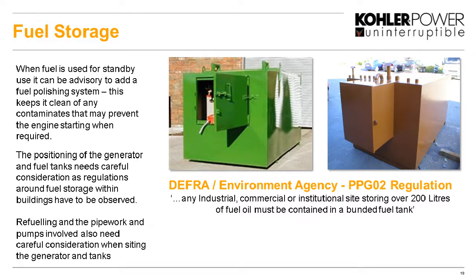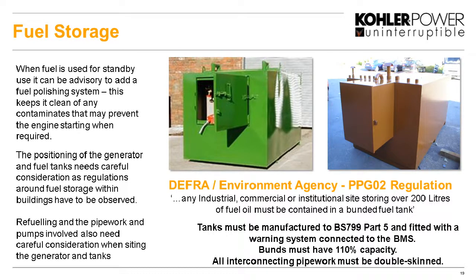Okay. One of the things about fuel storage is this is standby sets. This big tank of fuel might not be used for a long time, except for testing. So we have to make sure the fuel's in a good condition. So it can be advisable to have a fuel polishing system that we can actually clean the fuel with on a regular basis, to make sure that we can get rid of all the contaminants, which are typically water and sediment, from the fuel. If the fuel's no good, the engine won't start, and obviously that's very, very critical for a standby set.